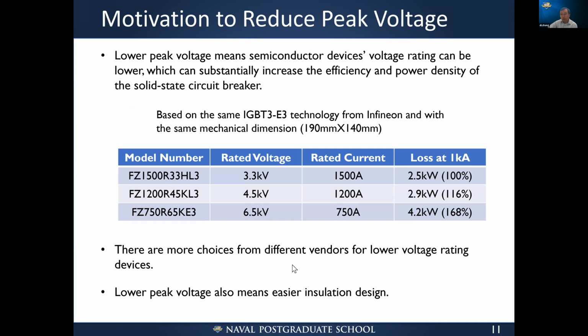So one way to do it is we just pick devices that can handle this. If 5 kilovolts is the peak, then we can pick devices that can handle 6.5 kilovolts. The job is done. However, there is a strong motivation to reduce the peak voltage. The reason is that lower peak voltages mean semiconductor devices with low voltage ratings can be used, and this can substantially increase the efficiency and the power densities of the breakers. And this is key to achieving NASA's very aggressive power density and efficiency target.